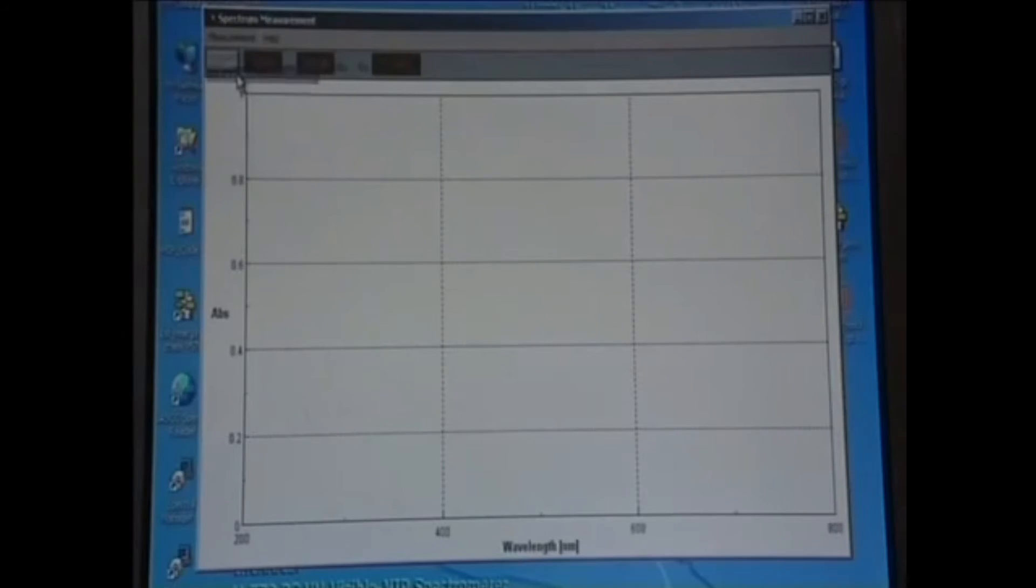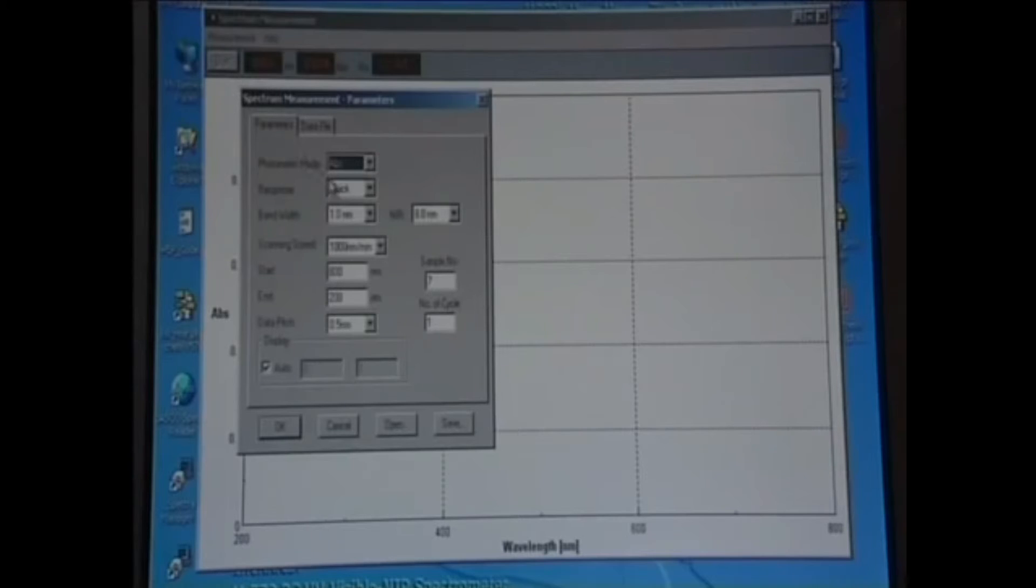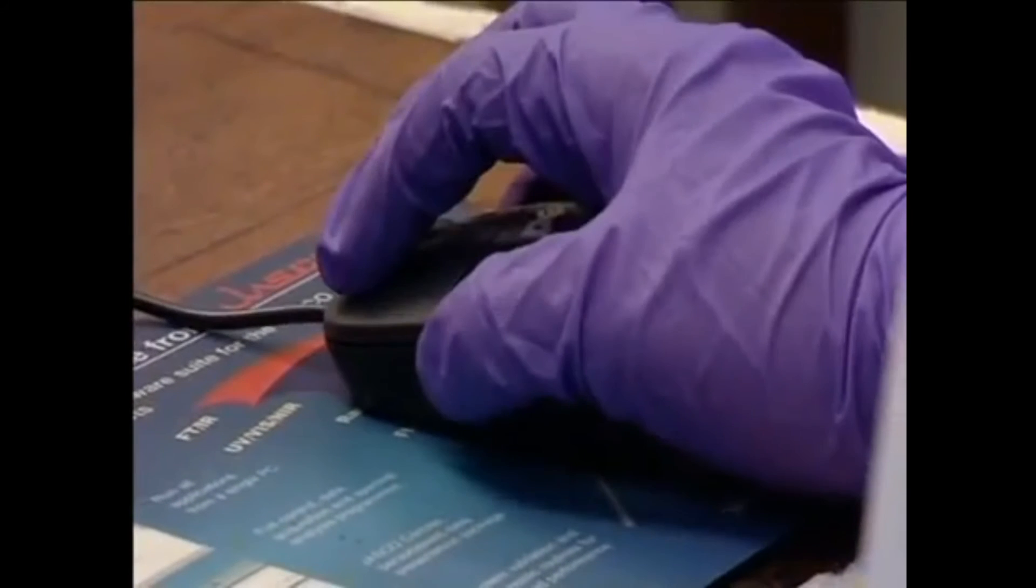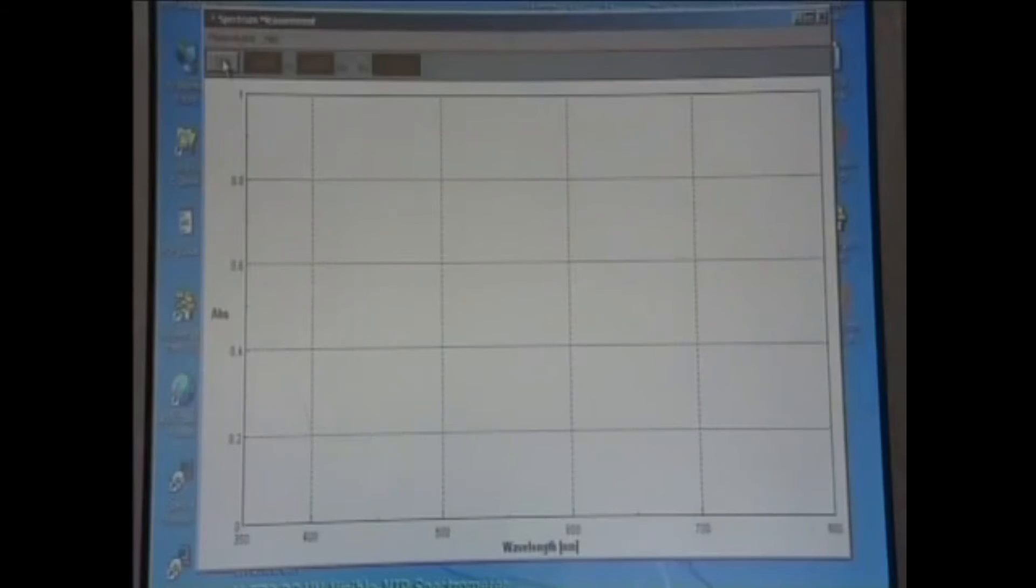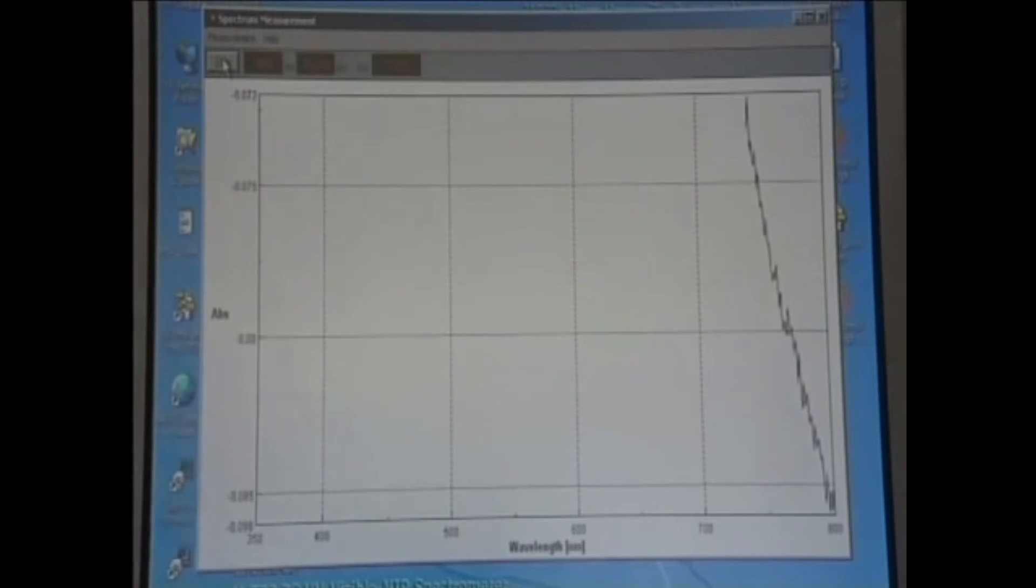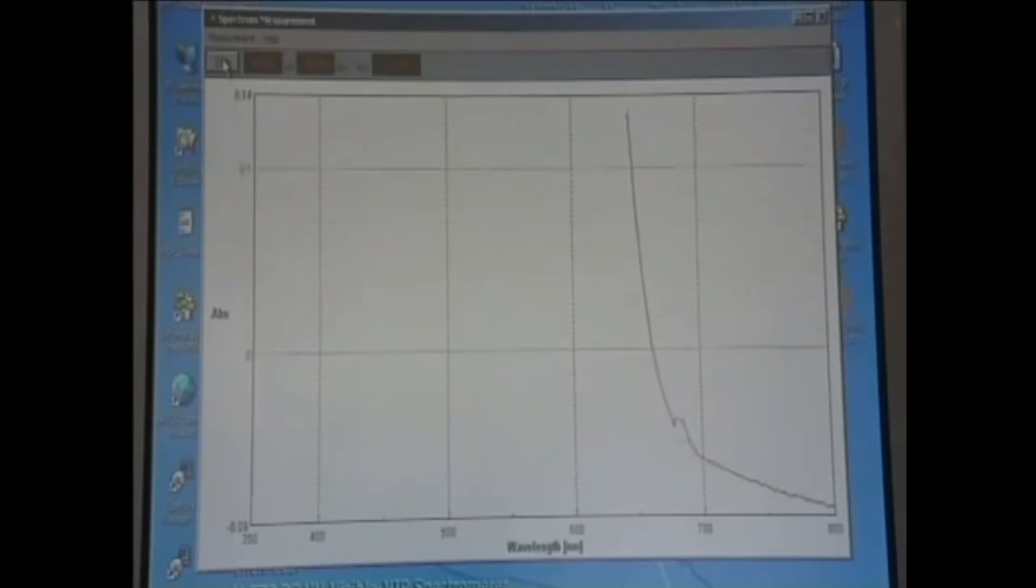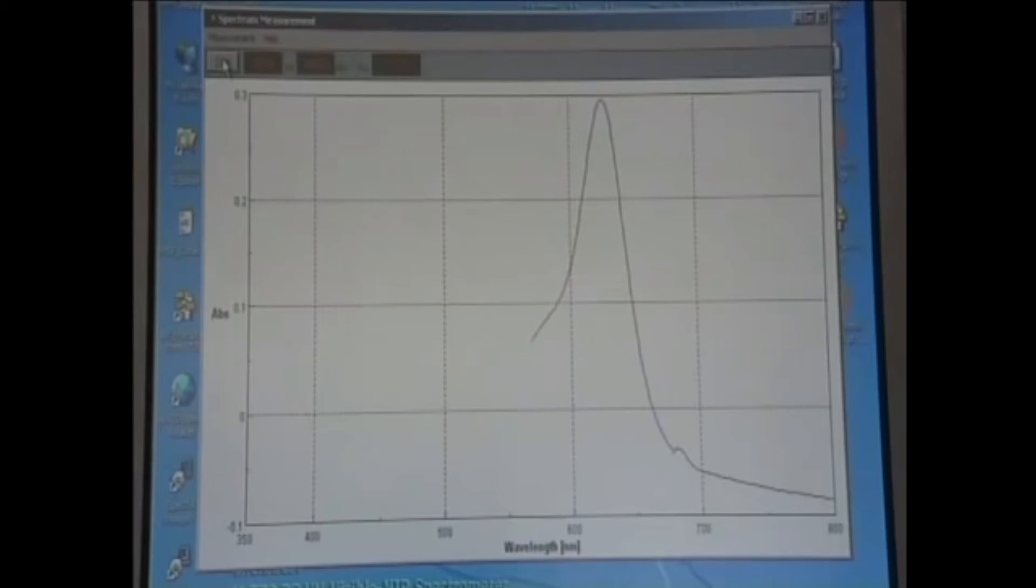The operator types details such as the wavelength range required and scanning speed into the computer that controls the instrument. He also zeros the instrument at a point where the sample does not absorb and then starts the scan. The spectrum appears on screen. The data is saved on the computer and a hard copy can be printed.